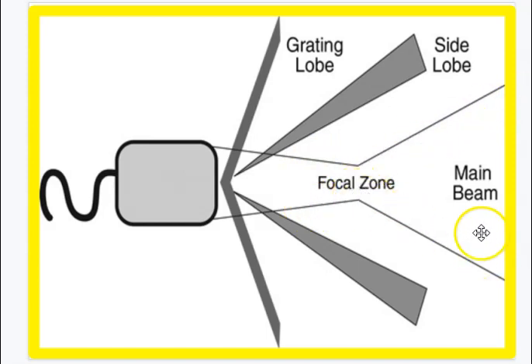Then it spreads out here, and this is where our lateral resolution would be challenged, and also our axial resolution would be here. Axial resolution would be better out here than lateral resolution due to the scan lines separating so much. But these are the side lobes that the ultrasound generates. It's just power that's coming out here, ultrasound's coming out of here, and you want to try to keep it as focused as much as possible. And you can do that with a larger lens, and perhaps even a concave lens you can really focus this beam down, narrow it out.